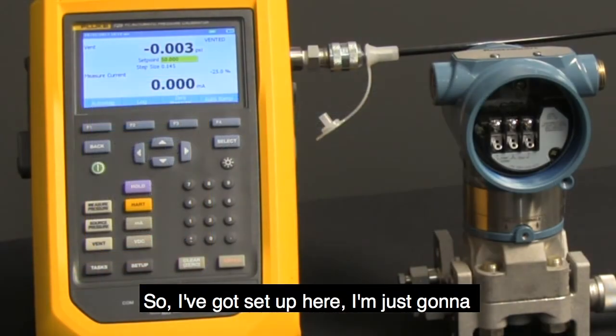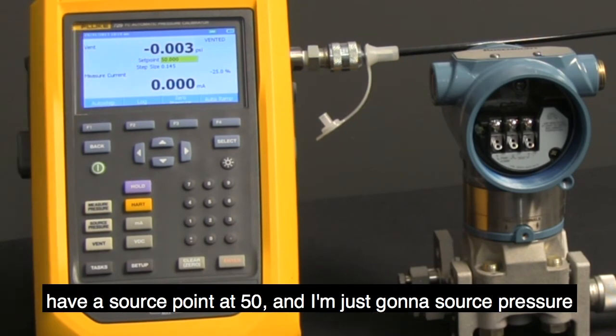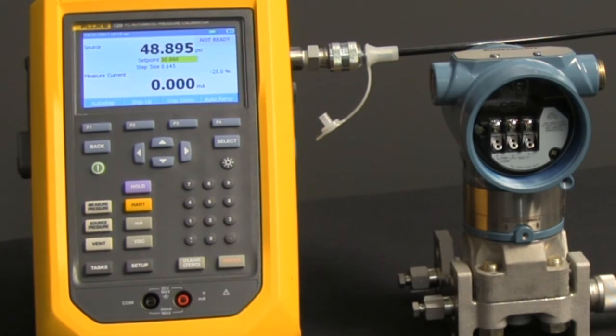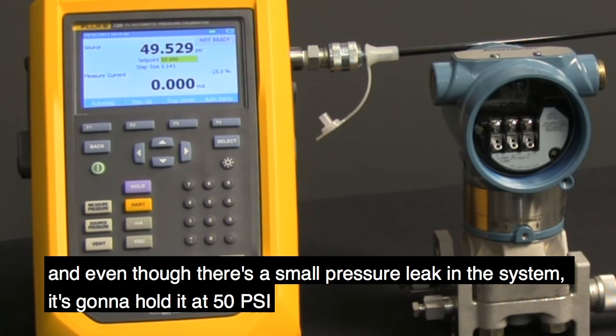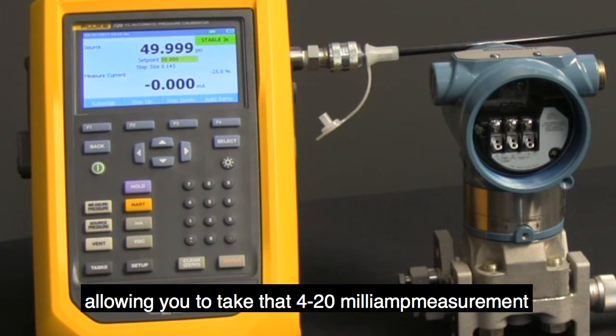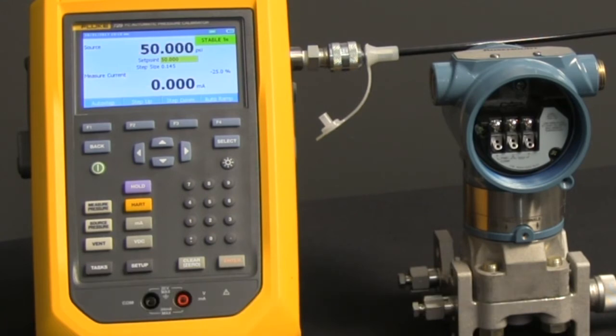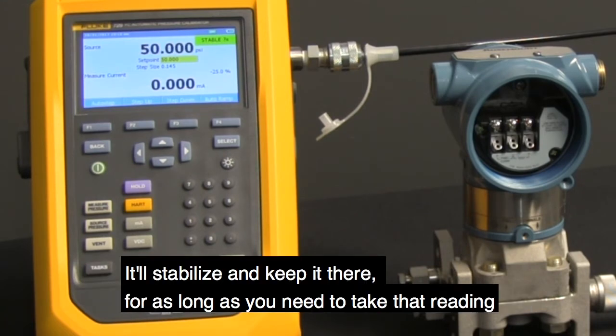I've got it set up here with a set point at 50, and I'm just going to source pressure. The 729 is going to bring that pressure up to 50, and even though there's a small pressure leak in the system, it's going to hold it at 50 psi, allowing you to take that 4-20 milliamp measurement. It'll stabilize and keep it there for as long as you need to take that reading.